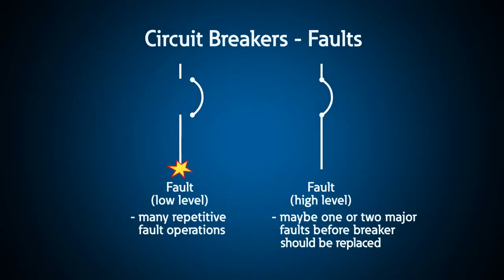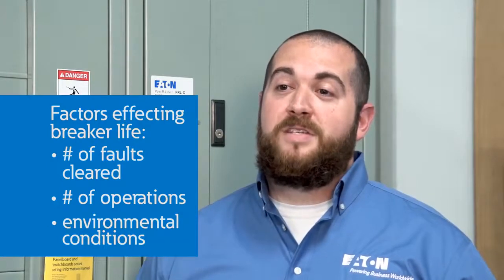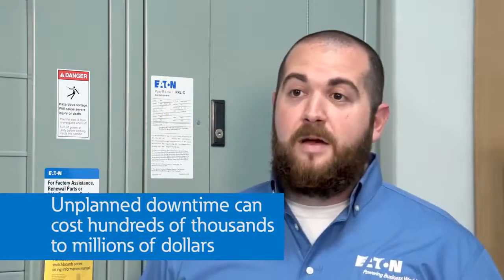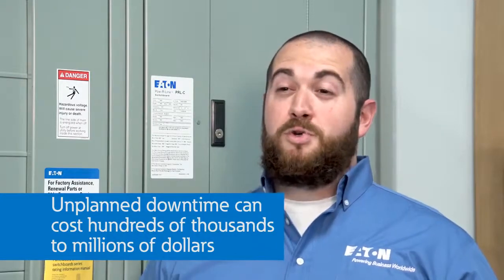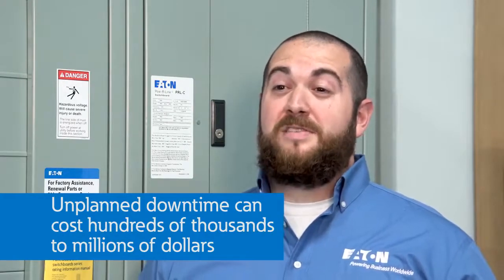Other breakers will see a really high short circuit fault, protect the system, but then need to be replaced almost immediately. Some breakers are in remote locations and no one ever turns them on or off. Other breakers get a lot of physical use as an on-off switch for a machine or a motor that can wear them down over time. There are so many factors that go into the life of a breaker. It would be nice to know exactly when a breaker needs to be replaced before an event compromises that breaker's ability to turn the power back on. Unplanned downtime for users like online tech companies, manufacturing plants, or wastewater treatment facilities could cost them anywhere from hundreds of thousands to millions of dollars and present safety issues.